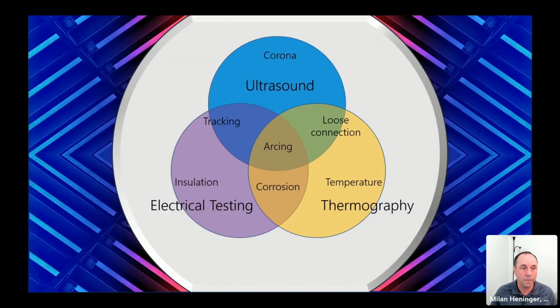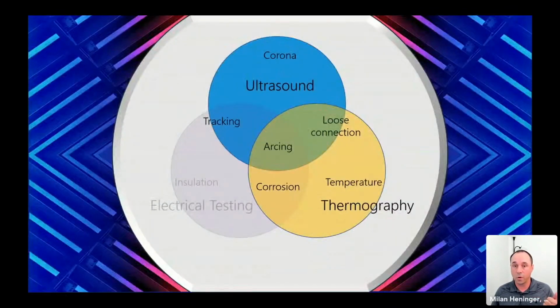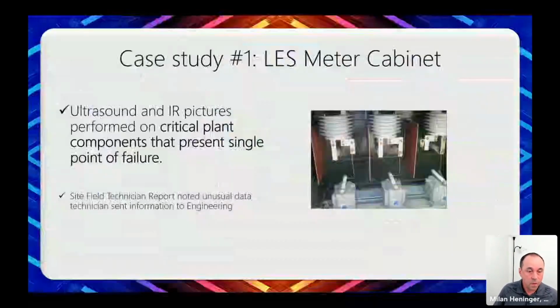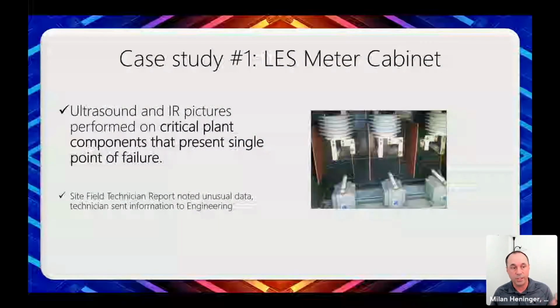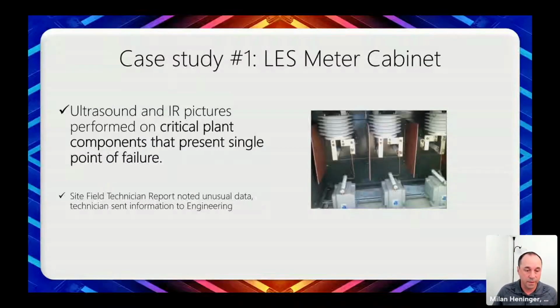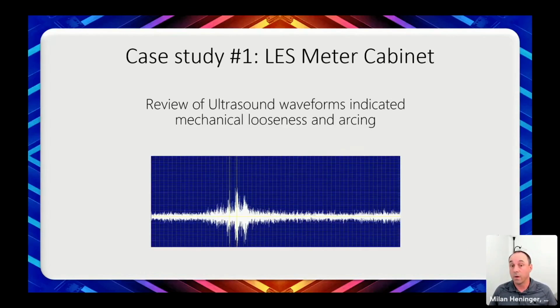So that narrowed us down very rapidly to 2 technologies that we deployed at the rest of the facilities. We went in with ultrasound and thermography. For our thermography, we went in both drone-based as well as with handheld cameras with the appropriate lenses. So you'll see that here. So at one of our first facilities, we did the ultrasound and IR, and we found an issue on this metering cabinet. When we reviewed the ultrasound, we saw that there was mechanical looseness and arcing, which is a pretty severe fault.